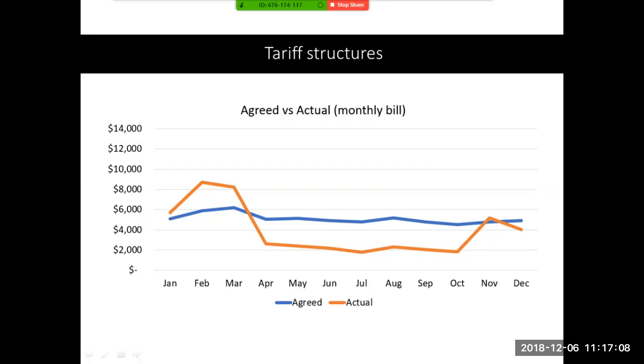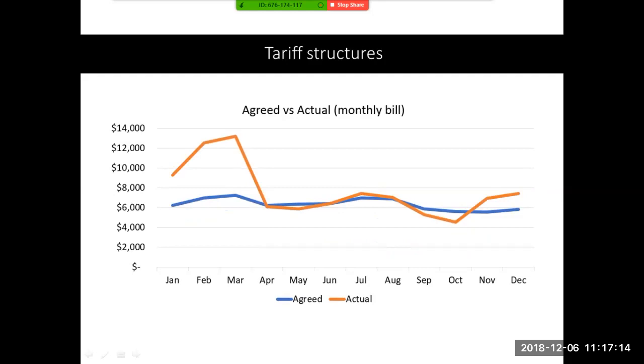But you have to run this information through a simulator to really figure out which one you're going to be better off on. This is winery 2 - similar situation, except this time the peak they've got is again quite high, but it drops down, not as much as previously. For this particular case, the actual and agreed time is roughly being charged at the same cost - it's just that they're paying extra money for an actual demand during the peak of vintage.